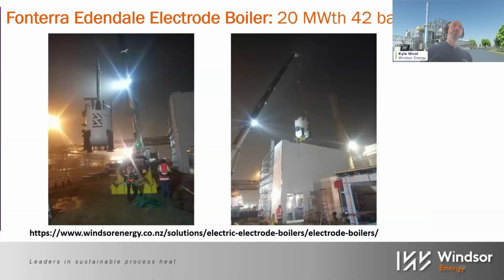Windsor was the EPC contractor for Fonterra's first electrode boiler, which is at Fonterra Edendale. So this is a 20 megawatt high pressure electrode boiler that produces 30.5 tonnes per hour of steam, and was officially opened last year. It also has a 99% thermal efficiency and a 25:1 turn down ratio.